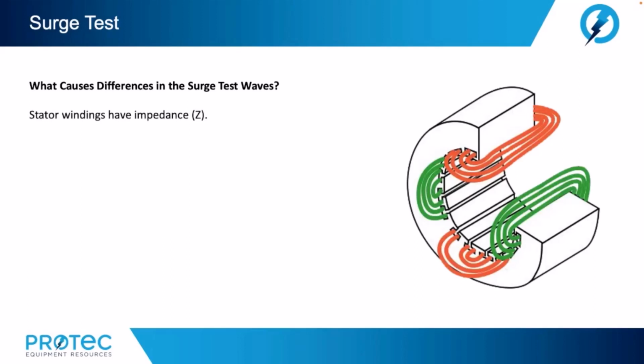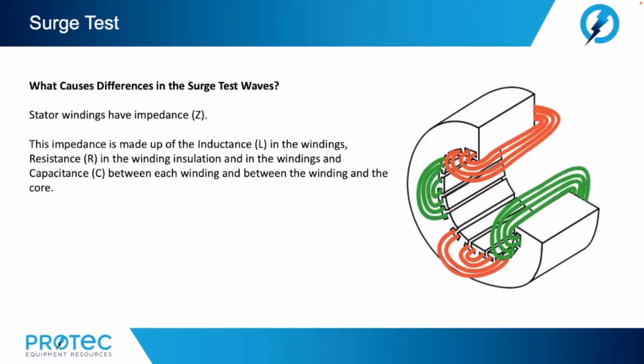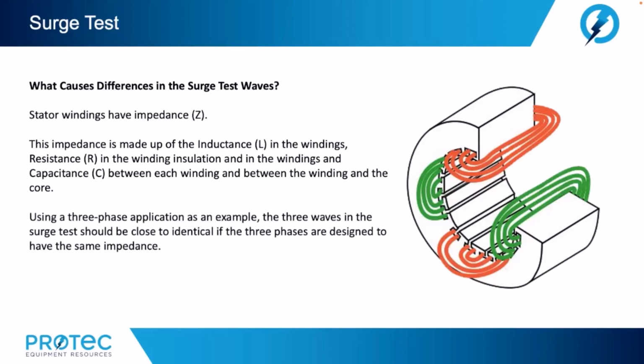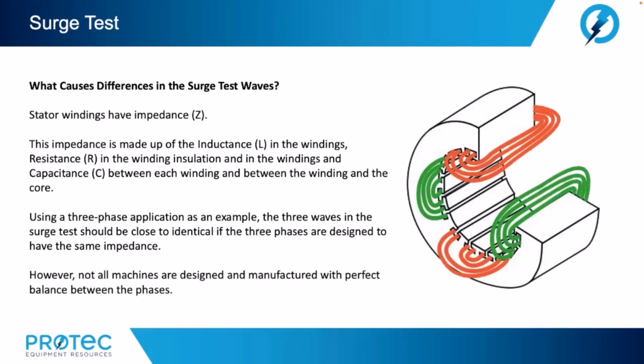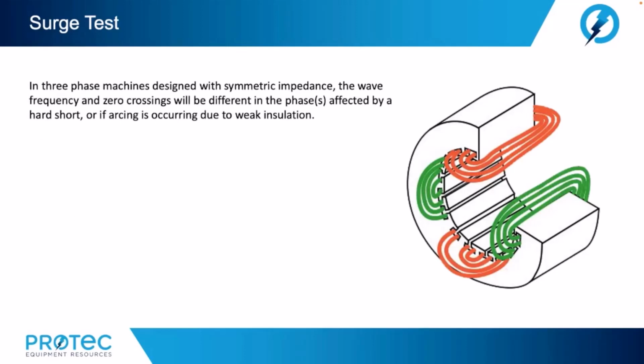Well, stator windings have impedance. This impedance is made up of the inductance L in the windings, resistance R in the winding insulation and in the windings, and capacitance C between each winding and between the windings and the core. Using a 3-phase application as an example, the 3 waves in the surge test should be close to identical if the 3 phases are designed to have the same impedance. However, not all machines are designed and manufactured with perfect balance between the phases. In 3-phase machines designed with symmetric impedance, the wave frequency and zero crossing will be different in the phases affected by a hard short, or if arcing is occurring due to weak insulation. The amplitude of the wave may also change.